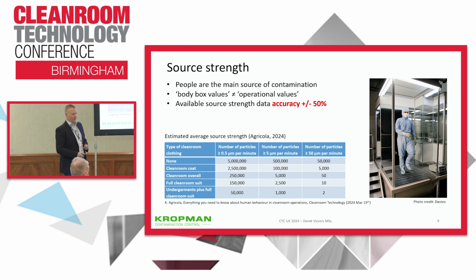I would probably say that you would test that at the highest flow, because that would typically be the worst efficiency that you will get. Right. But the filter efficiency would change with a different... It would, but it would potentially get better with lower flow. HEPA manufacturers are probably able to give us more information, but my thoughts would be that typically the more air you put through a filter, the more likely you are to get leaks through it. So in that system, I would have set up and tested it at the maximum capacity flow for the system, and then if it backs down, you improve the efficiency.